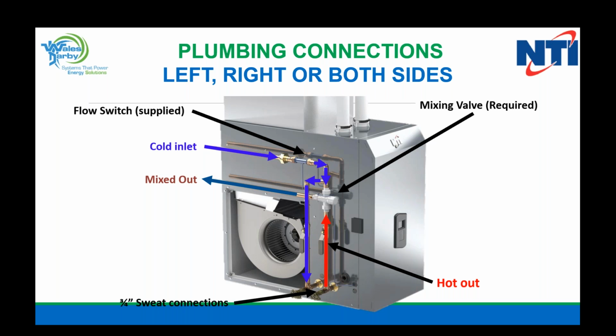If we get to higher flow rates, again, this will prioritize hot water. When it gets to about 170,000 BTU, it will reduce the heat, knock it off, and divert all the power that the burner's producing, all the BTU that the burner's producing, and drive that hot water demand to where you need it to go. So that's key, very important.